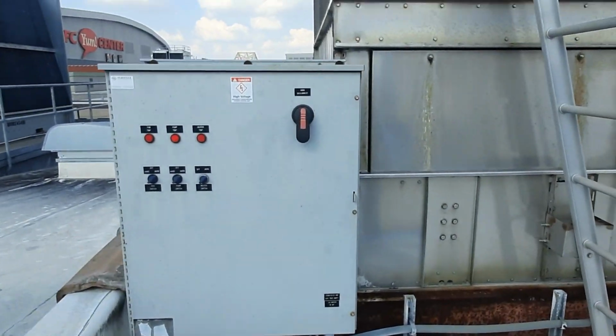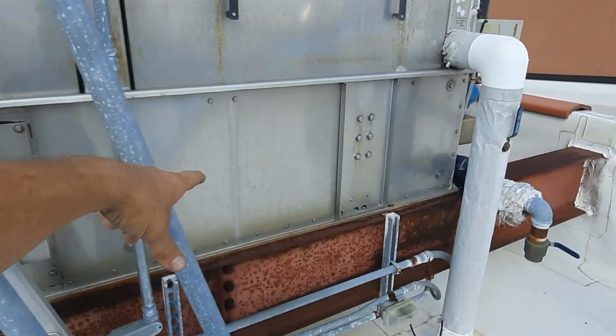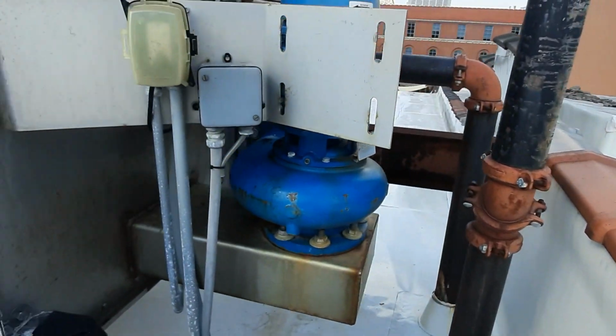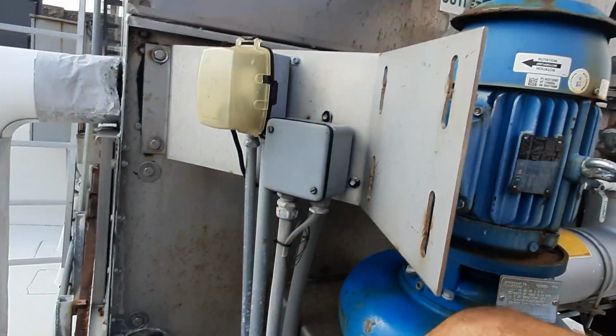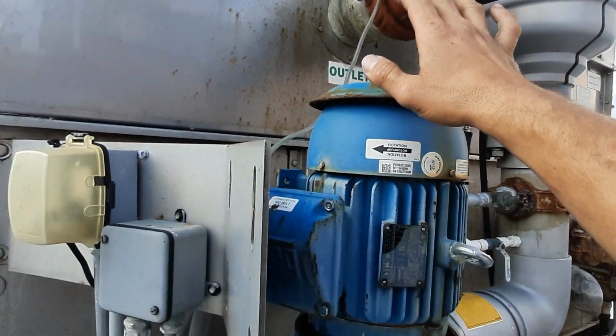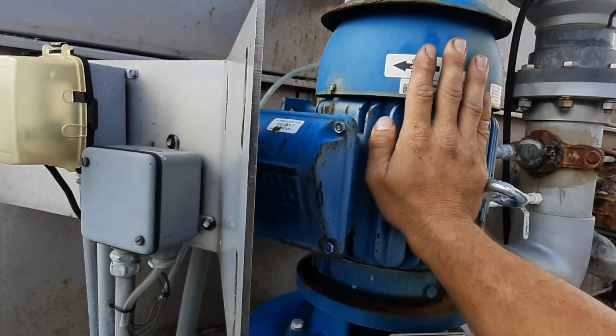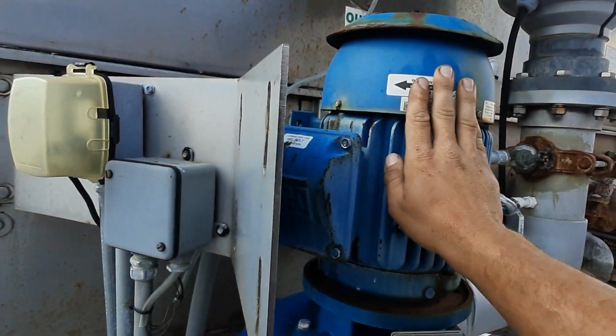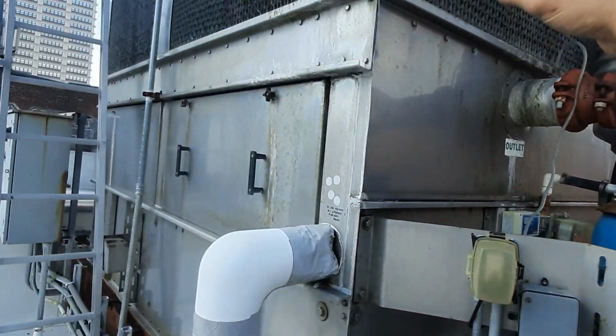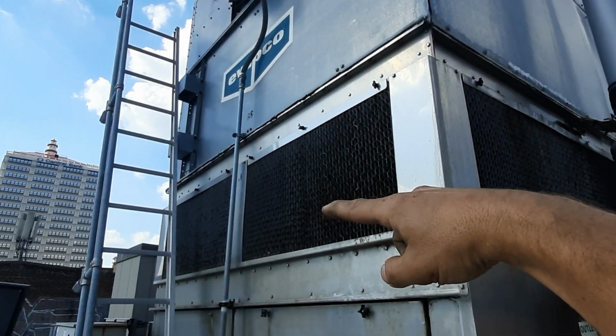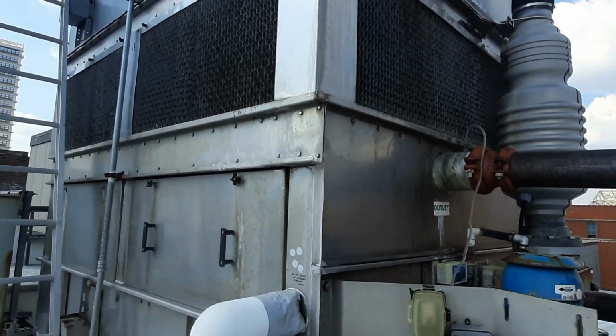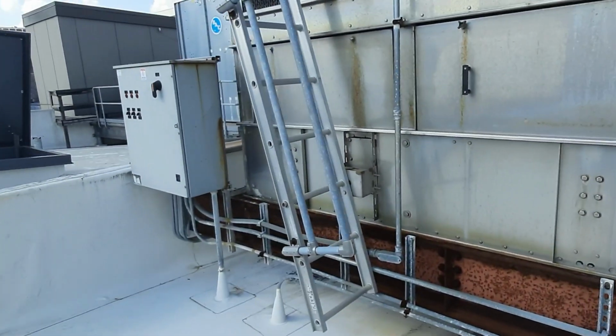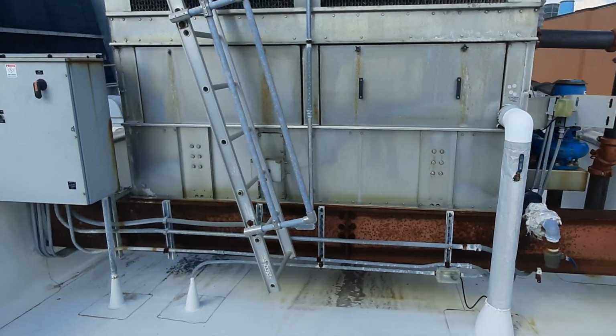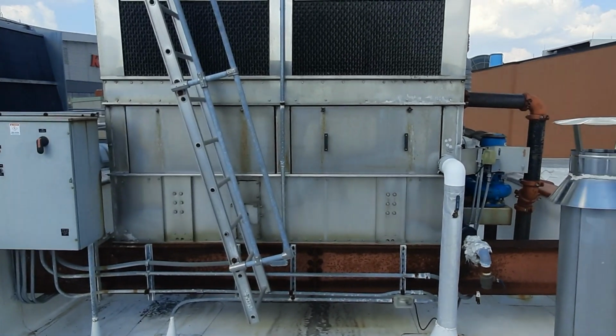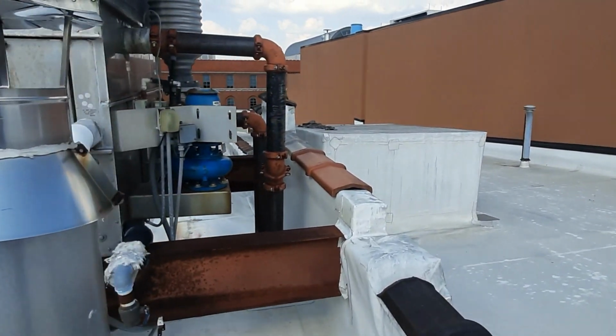So here is how we keep our water cool. We got a cooling tower. This is our sump here. Two stages. Thermostat inside of here senses the outlet water temperature. And the pump comes on at, say, 80 degrees, 82 degrees. As the water continues to warm up, we got a fan motor up there that draws air through to help cool that water down more. And we maintain around that 80 degree water, which mimics about an 80 degree day outdoors on our condensers inside. So, pretty simple process when you know how it works.